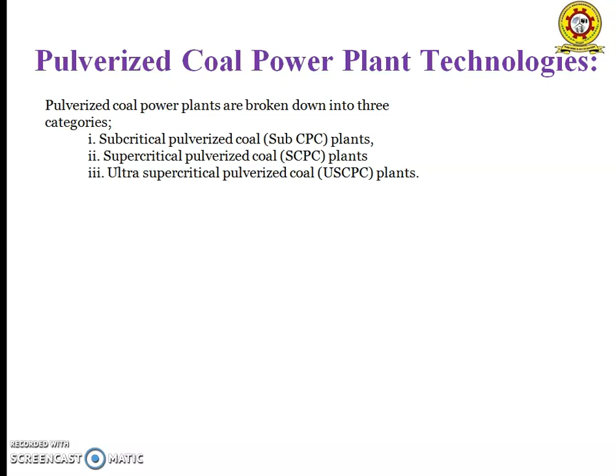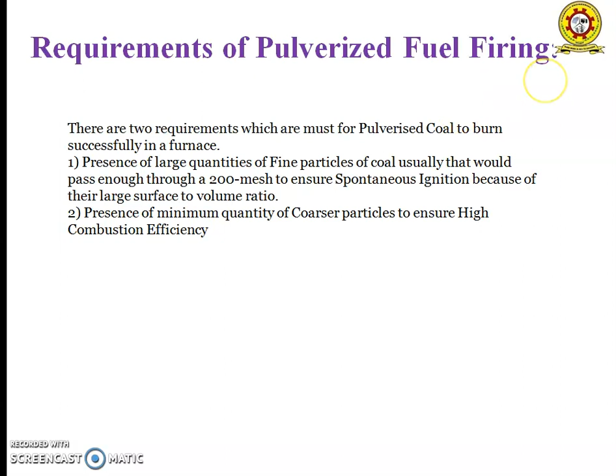Requirements of pulverized fuel firing. There are two requirements which must be met for pulverized coal to burn successfully in the furnace. First one is the presence of large quantities of fine particles of coal, usually passing through a 200 mesh, to ensure spontaneous ignition because of their large surface to volume ratio. And second one is the presence of a minimum quantity of coarser particles to ensure higher combustion efficiency.